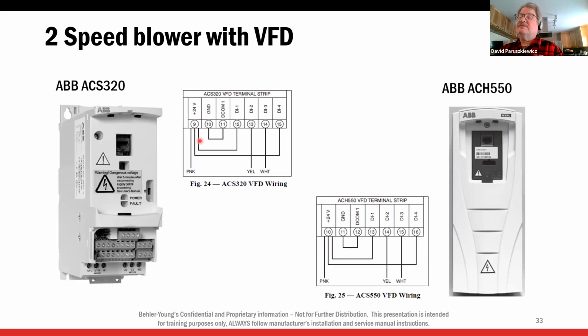that means it's not calling, right? Because if this is closed, I wouldn't have voltage. Then I'm going to check from here to here. Do I have voltage? No. So that means this one's closed. So I should have blower running. Now I could also go to ground. So we just check, do I have power on either one of these inputs here? If I do, the blower should be running. Pretty much, don't know how much simpler that can be.